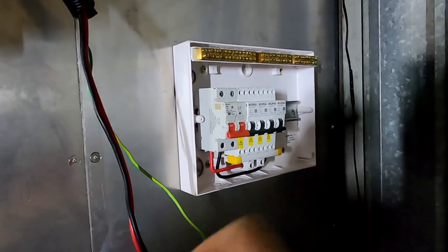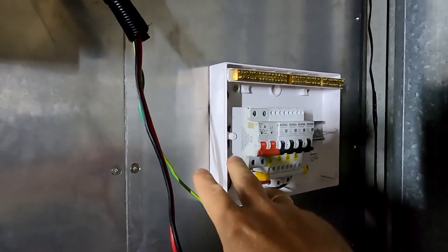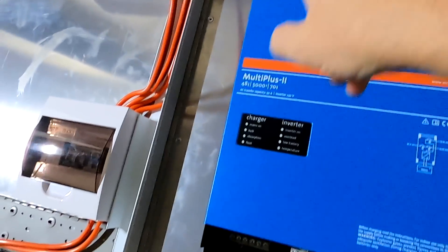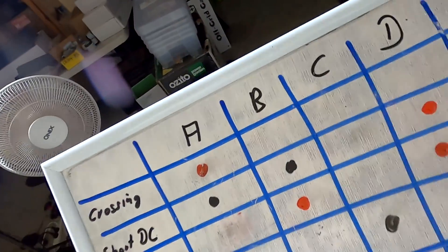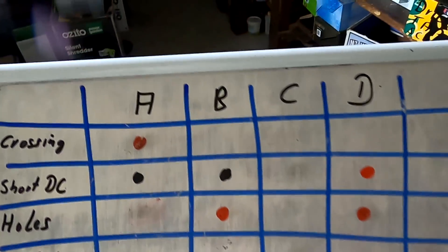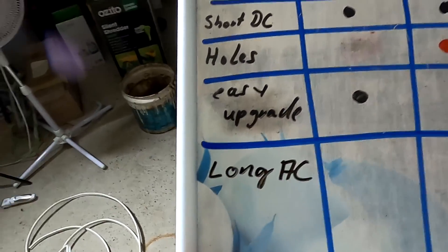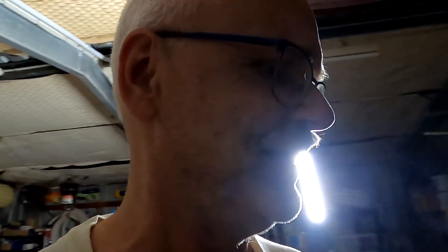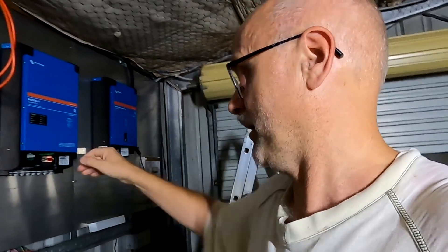I have also mounted the AC distribution box here on this side already and have done all the measurement. So we will have the 50 by 50 cable duct here as well. And then going above the inverters coming down to this inverter and coming down here to this inverter. So no crossing, no holes. I made myself actually a little matrix here with the solutions A, B, C and then had different criteria there for crossing, short DC cables and easy upgrade, holes, long AC cables and all that kind of stuff. And then I said, what's the possibilities? What's the benefits of having this solution over this solution? And C is really the best solution because of the possibility to upgrade the system further down the track. We don't have to deal with any holes in the aluminum sheet, which we cannot use anymore with future upgrades. And we certainly don't have any crossings from AC and DC low and high voltage anywhere.